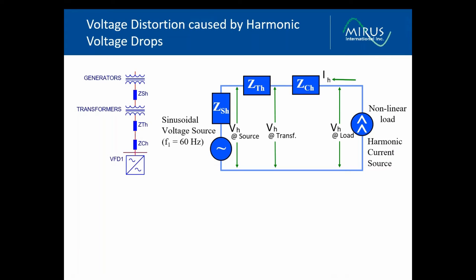In the interest of time, I will assume that most of you, if not all, are familiar with how VFDs introduce harmonic currents on our power systems. I will, however, take a few minutes to describe how these harmonic currents will create voltage distortion, especially on systems with high impedance, as is the case in marine applications where generators are the power source.